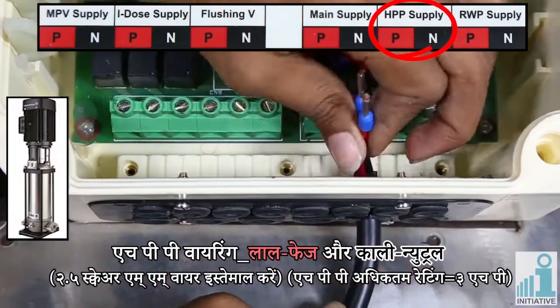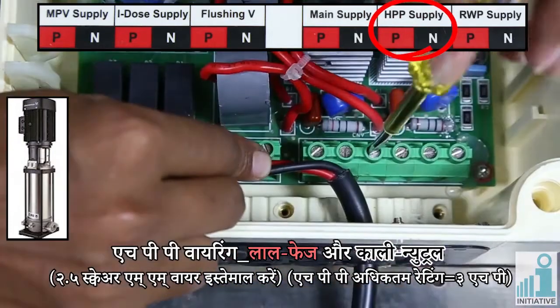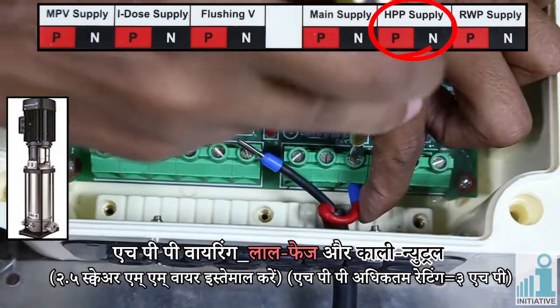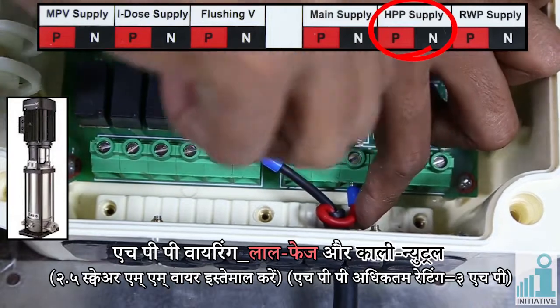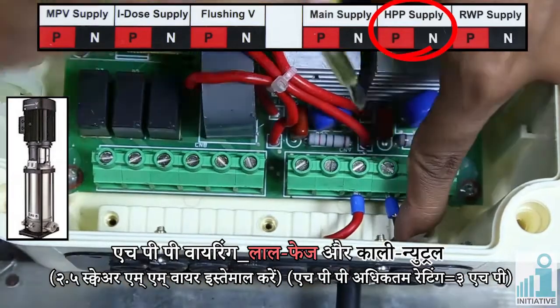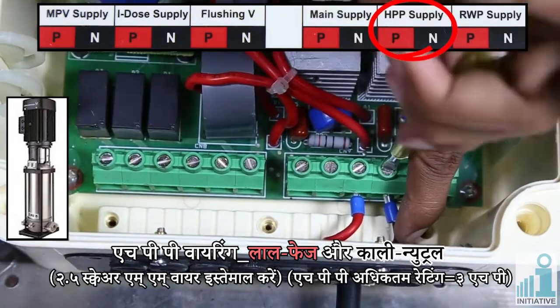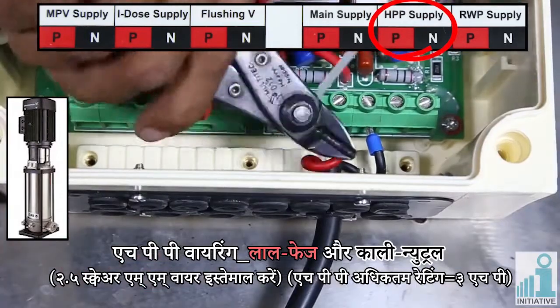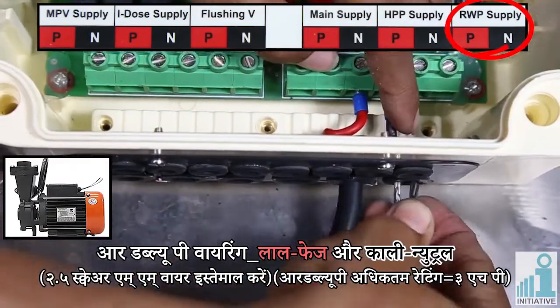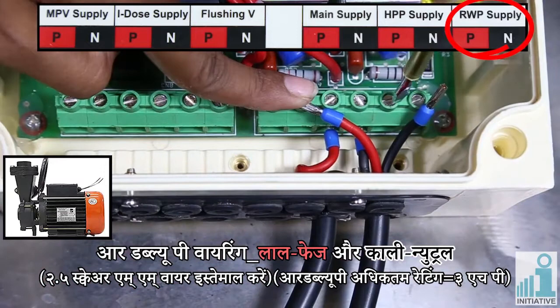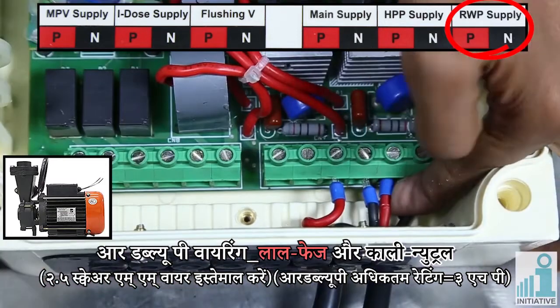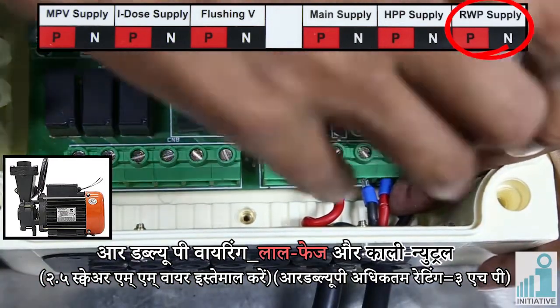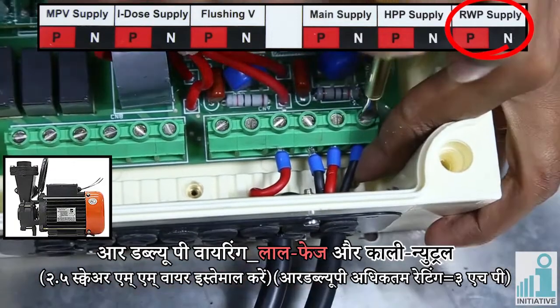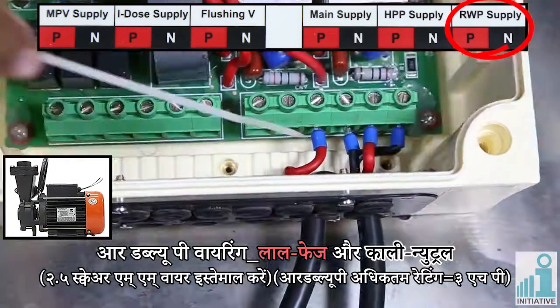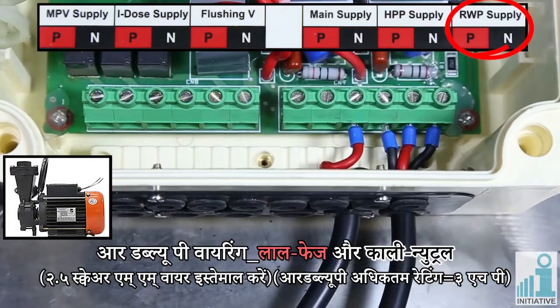HPP wiring. Red in phase and black in neutral. Please use 2.5 square mm wire and HPP max rating should be 3 HP. RWP wiring. Red in phase and black in neutral. Please use 2.5 square mm wire and RWP max rating should be 3 HP.